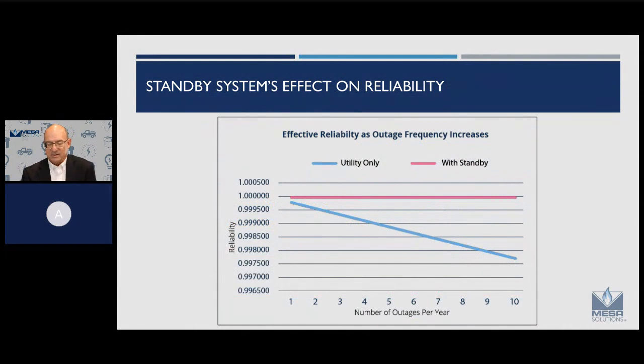Graphing this out, it looked like the simplest way to show some comparisons is to look at different cases of the number of times per year that the utility experiences an outage. What this shows pretty dramatically is that the effective reliability of just the utility goes down in a straight line as the number of outages increases. But with a standby system, the overall reliability to the load stays very near 100%.